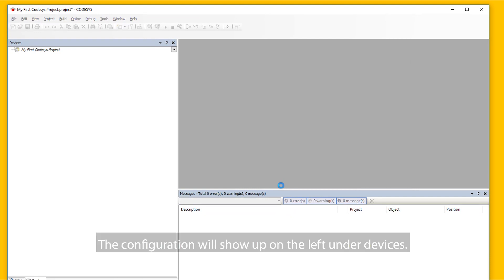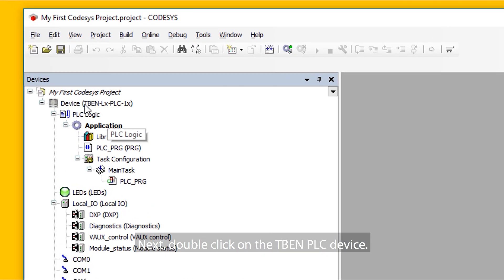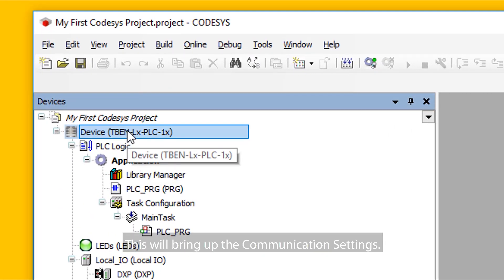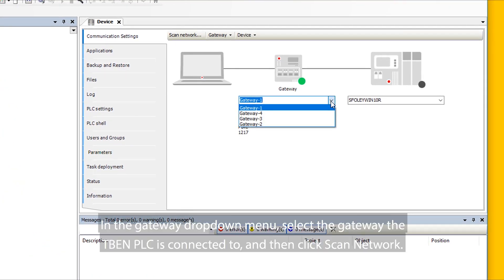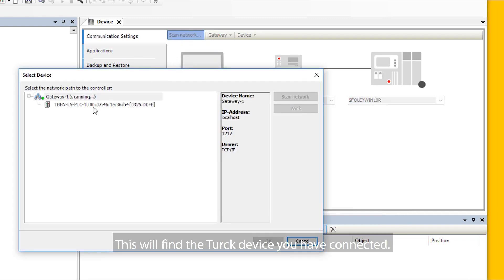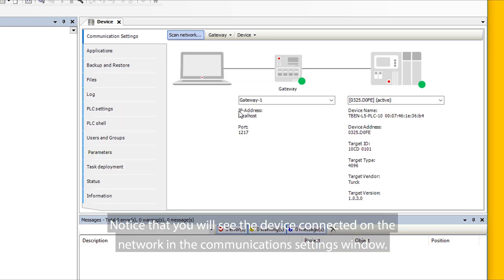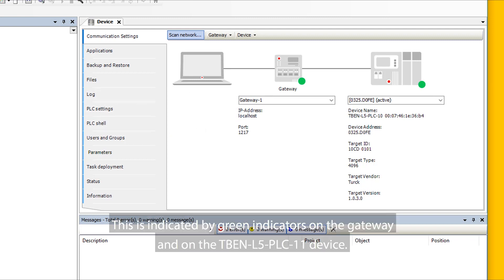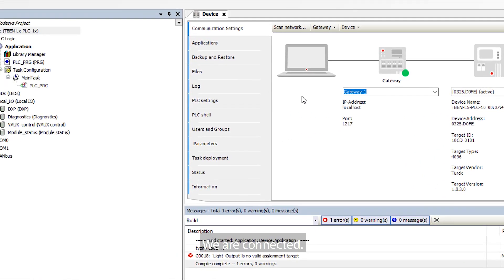The configuration will show up on the left under Devices. Next, double-click on the TBEN-PLC device. This will bring up the communication settings. In the Gateway drop-down menu, select the gateway the TBEN-PLC is connected to and then select Scan Network. This will find the Turck device you have connected. Click on the device and select OK. You will see the device connected on the network indicated by green indicators on the gateway and on the TBEN-PLC device — we are connected.